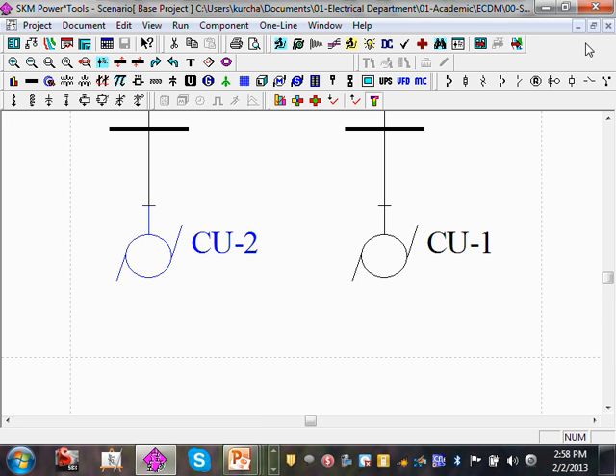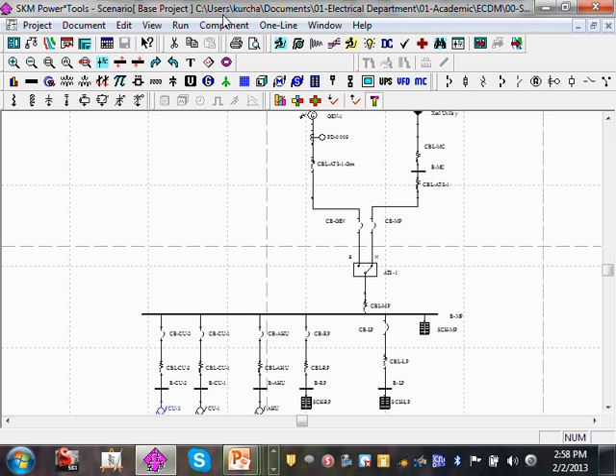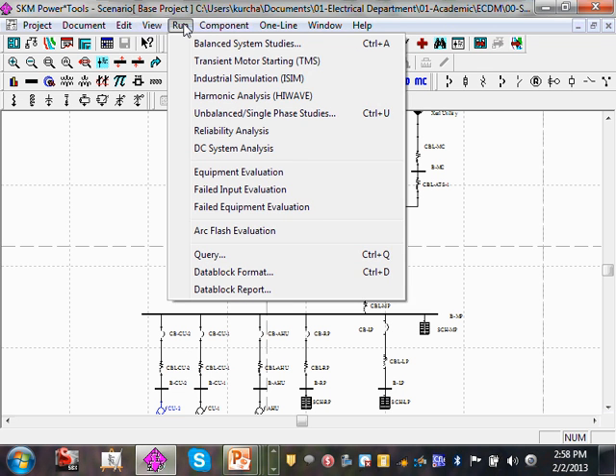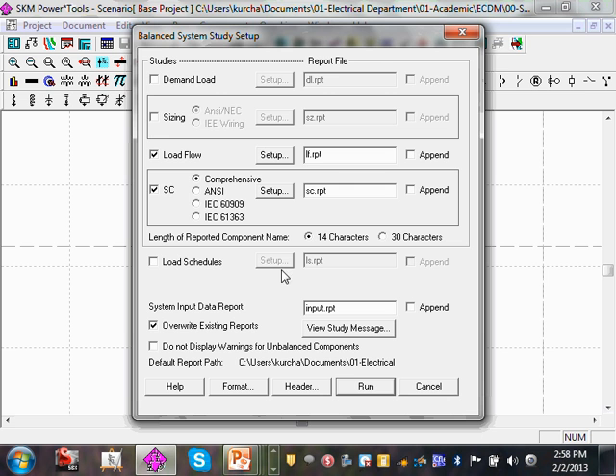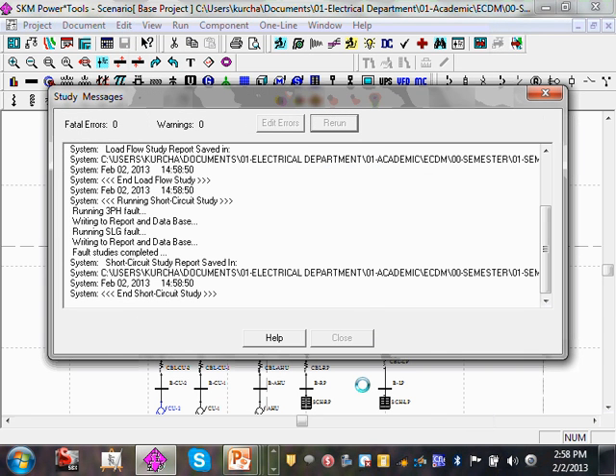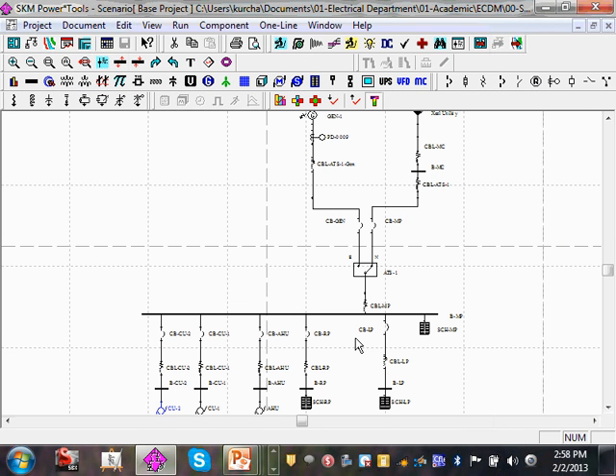So when you do that, my friends, I'm just going to take you to run. Here's your run, balanced 3-phase circuit. And this is how you run load flow and short circuit right here. For every system, you put in the impedance. It's as easy as doing the calculation for you. You guys are supposed to do it by hand. I have a handout for you. So now my short circuit calculation is done.